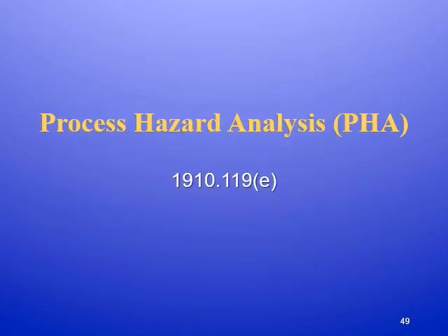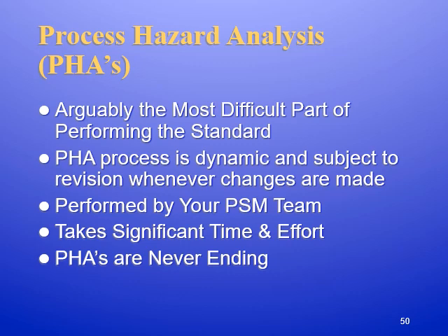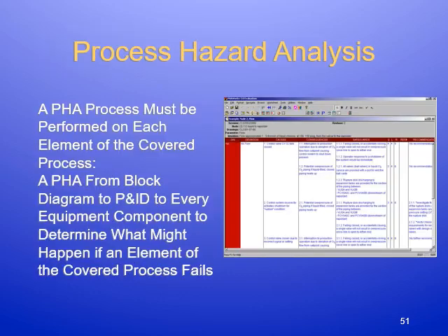Process hazard analysis. This is the most difficult yet most important part of the standard. So PHA is dynamic, which means it's always changing. It's subject to revision whenever you make changes. It's performed by your PSM team, which you put together. Like I said, this is not a one-person effort. This takes significant time and effort, and PHAs, process hazard analyses, are never ending.